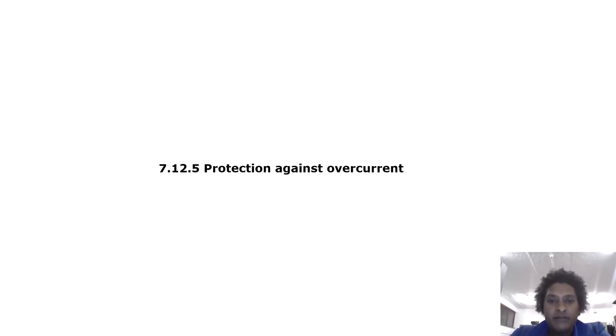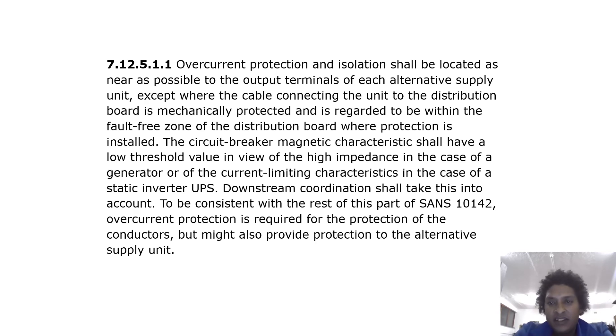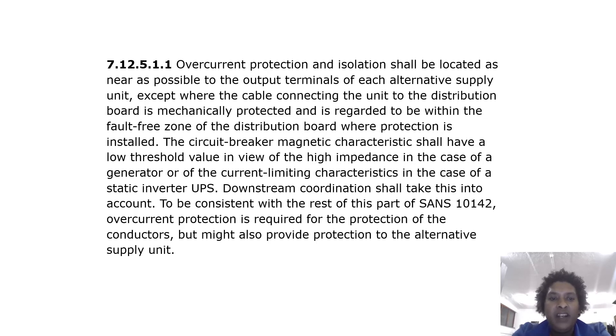Overcurrent protection and isolation shall be located as near as possible to the output terminals of each alternative supply unit, except where the cable connecting the unit to the distribution board is mechanically protected and is regarded to be within the fault-free zone of the distribution board. The circuit breaker magnetic characteristic shall have a low threshold value in view of the high impedance in the case of a generator, or the current-limiting characteristics in the case of a static inverter UPS. Downstream coordination shall take this into account; overcurrent protection is required for the protection of conductors but might also provide protection to the alternative supply unit.